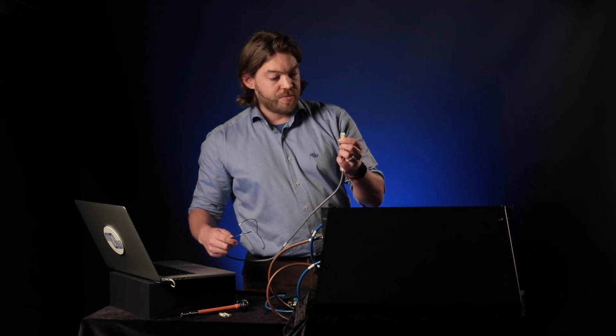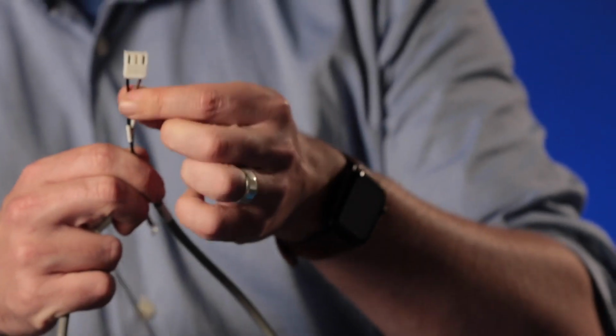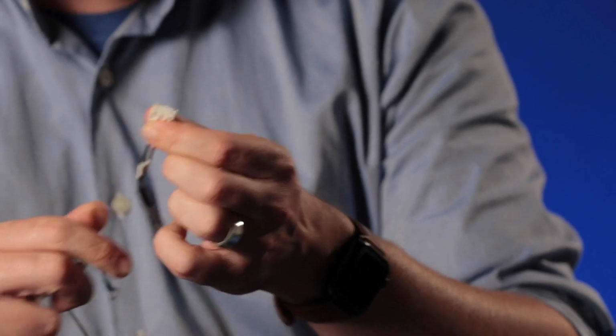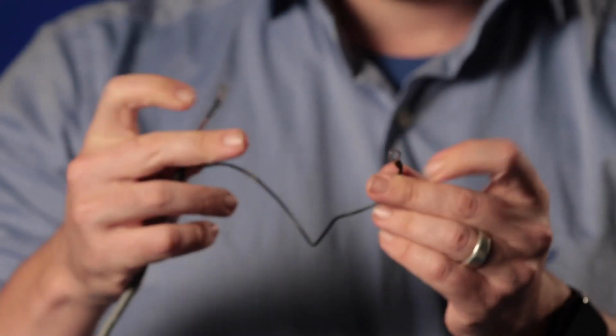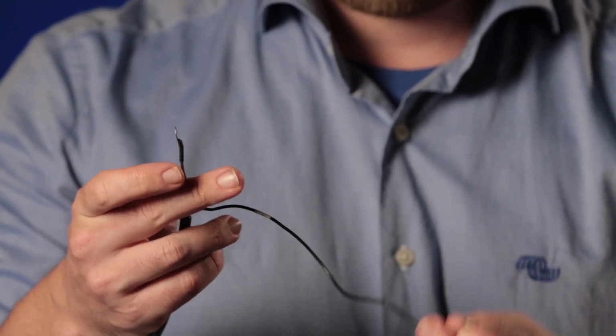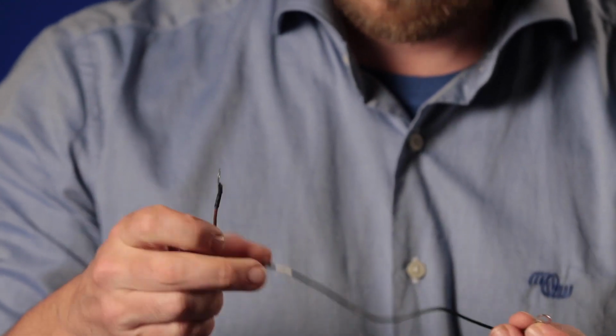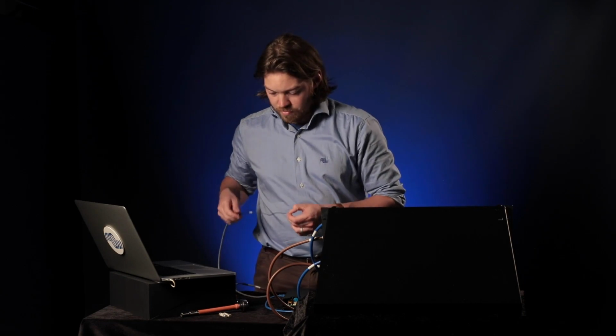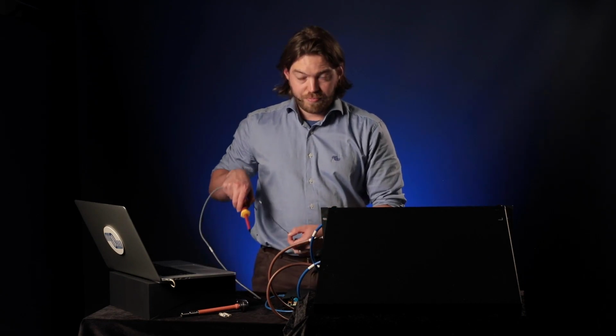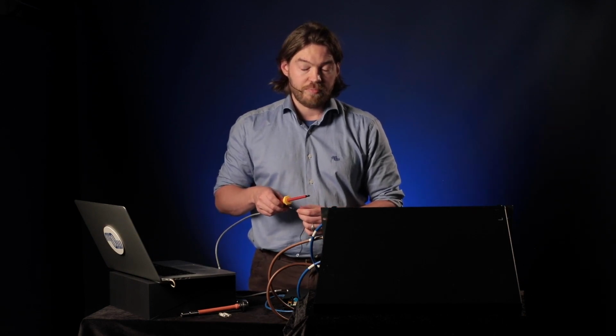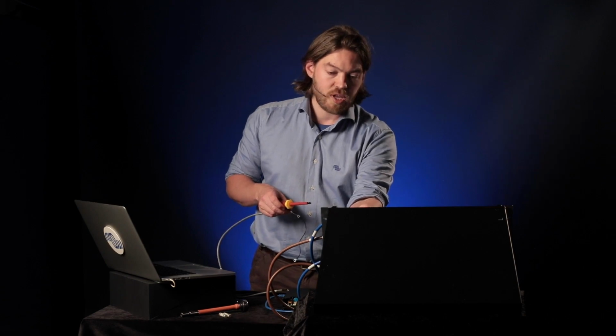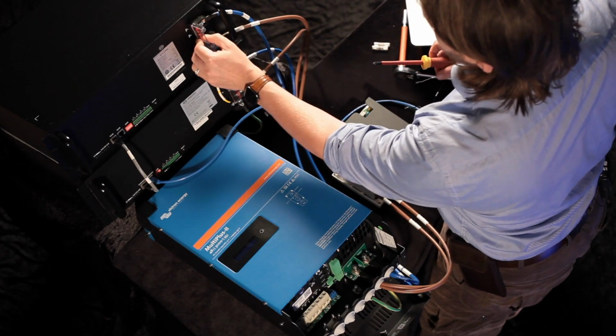This is the cable, already crimped with its special keyed plug on this side. On this side we have the positive and negative connectors - positive being brown and labelled, negative being black. If you have a proper DC bus, you'd connect this to the DC bus. It may come pre-wired into your Victron or BYD battery box, but in our case I'm going to take some power off the batteries to power this unit.